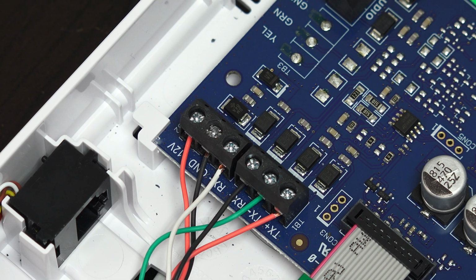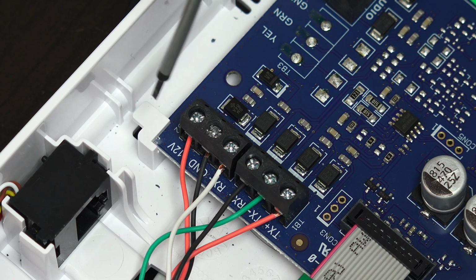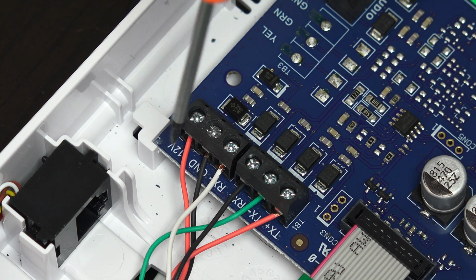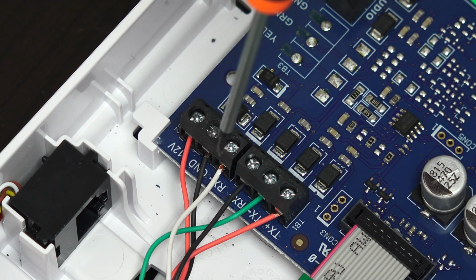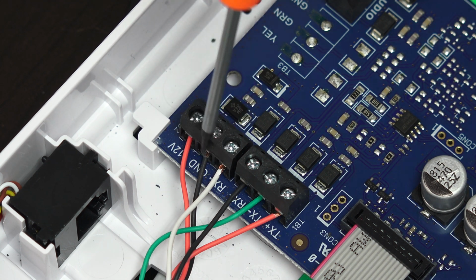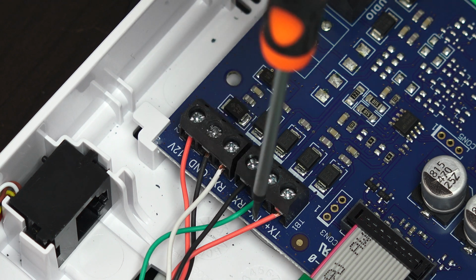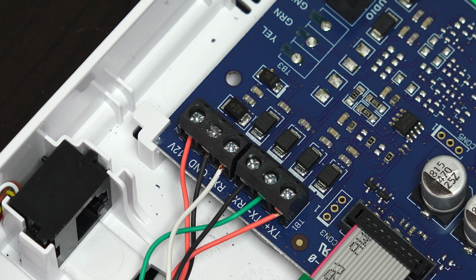So I just wanted to point out the six wire connections that you'll have at the NEO communicator. Starting on this side, we have the 12 volt connection, the positive power connection. So that's using the red cable. And then we have the ground connection, the negative power connection, which is using the black cable. The other four colored cables don't really matter as long as they match up at the PCL422, which I'll point out in a second.